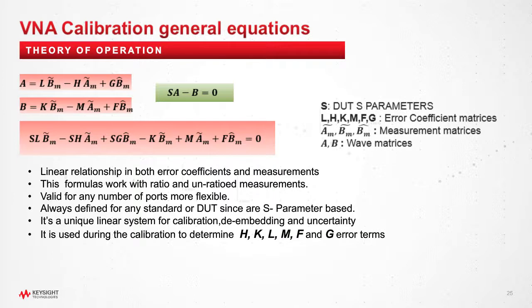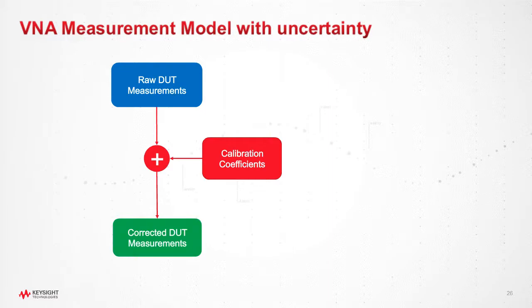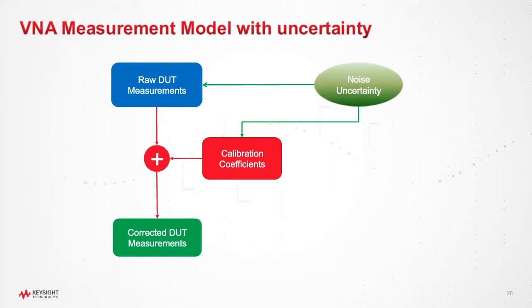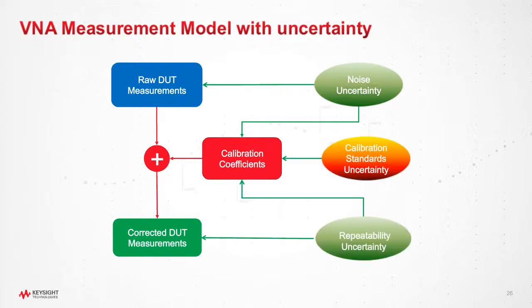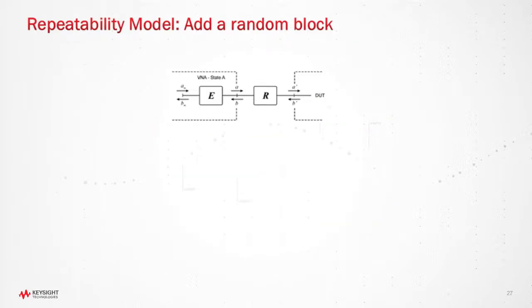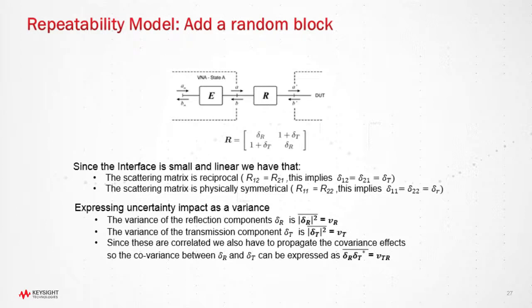So now let's come to the S parameter with uncertainty. In the case of uncertainty, we have exactly the same model, but we have to add uncertainty. In this case, we're going to add uncertainty in the form of noise, in the form of calibration standard uncertainty, and in the form of repeatability. So let's start from the repeatability. The repeatability can be modeled in terms of a random path attached to our VNA, which of course has some random number in the reflection, a random number on the transmission. Since the interface is small, we can assume the variance of the reflection coefficients, the variance of the transmission coefficients, and their covariances.